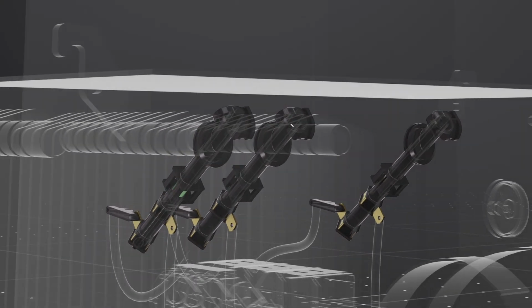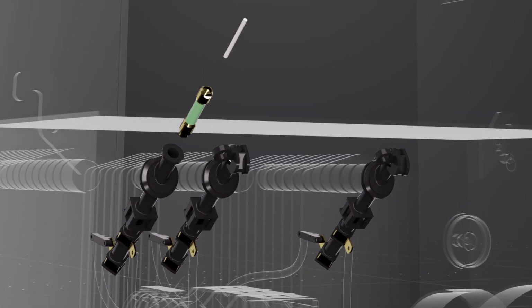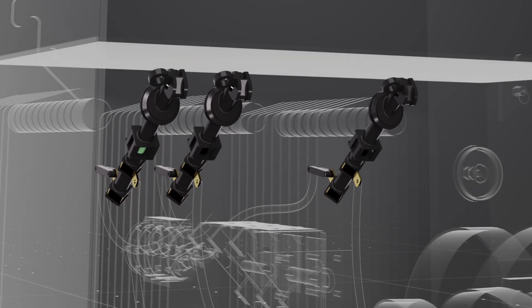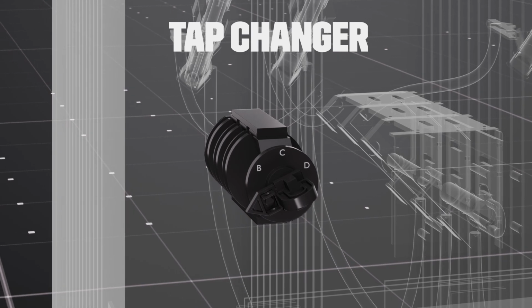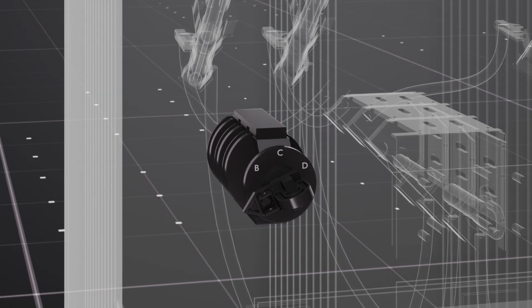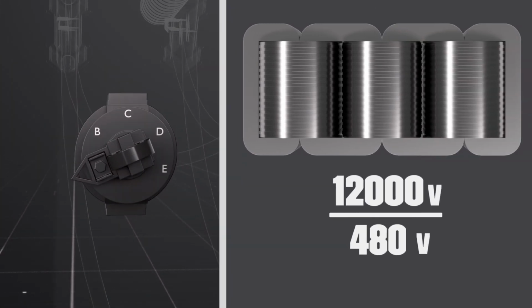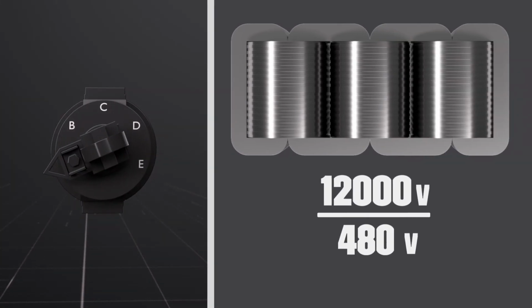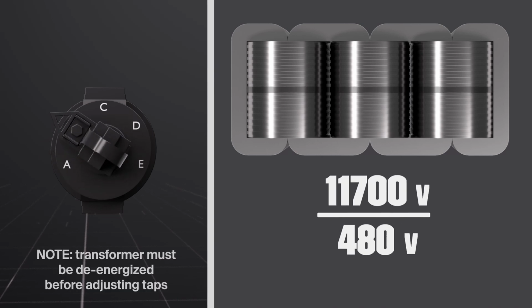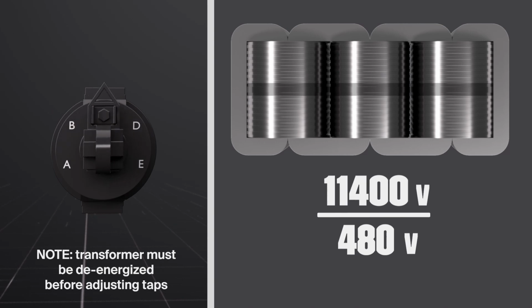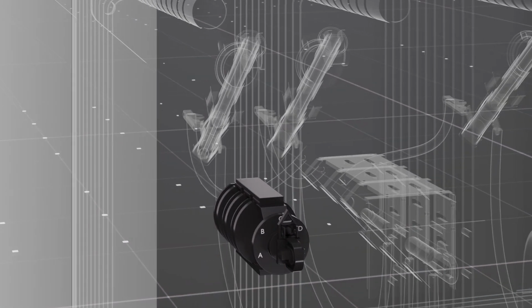When exposed to high current or high heat, a thin wire within the fuse, called the element, melts, effectively opening the circuit and disconnecting the transformer from the power source. Once the issue that's caused the fuse to blow is resolved, the fuse can be removed and replaced. Voltage adjustment taps allow you to maintain the correct secondary voltage in case the primary voltage is higher or lower than expected. The tap setting on the transformer is adjusted by rotating the tap changer. As the tap changer is rotated, small sections of the primary windings are disengaged, which alters the ratio of primary to secondary windings, thereby lowering the primary voltage rating.